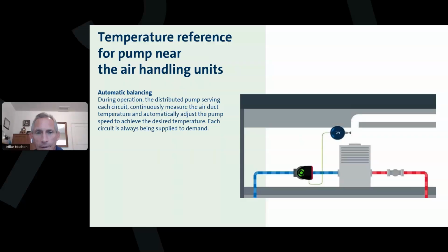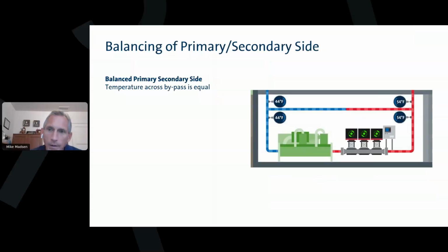I think I might have made it through them all. Oh, there's some more. Is this also applied to hot water pumping? Yes, we said that to help lower the return water temperature. Oh, for condensing boilers. Yeah, sometimes the return water temperature is too high and the condensing boilers don't condense. I would think that would work for that.